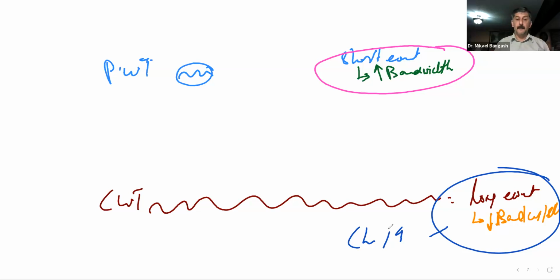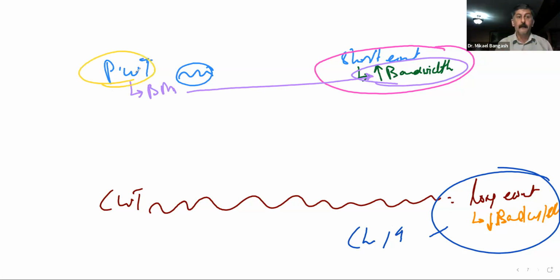But for now, just remember: in a pulse wave transducer, what did we have? We had a backing material, and one of the consequences of that backing material was that it gives us the great bandwidth. The main reason that we had backing material was so that we could produce a pulsed wave, where pulses are always short events. Did you girls get that?